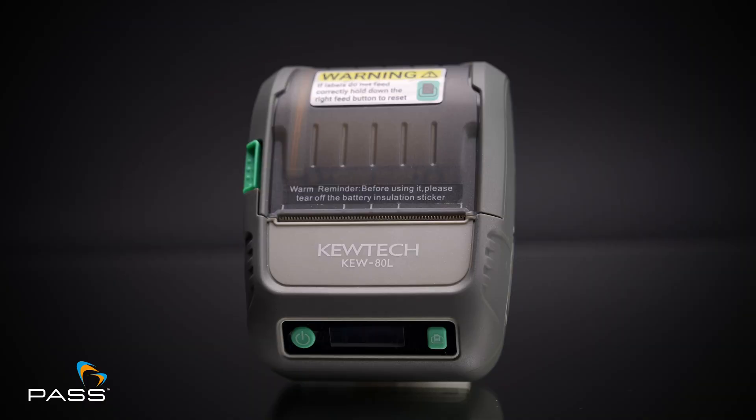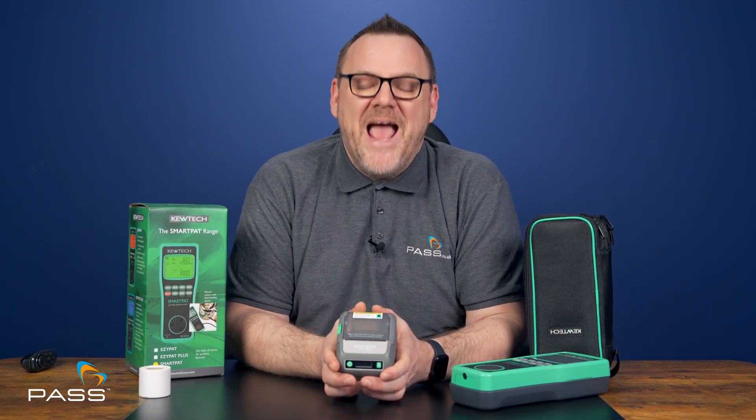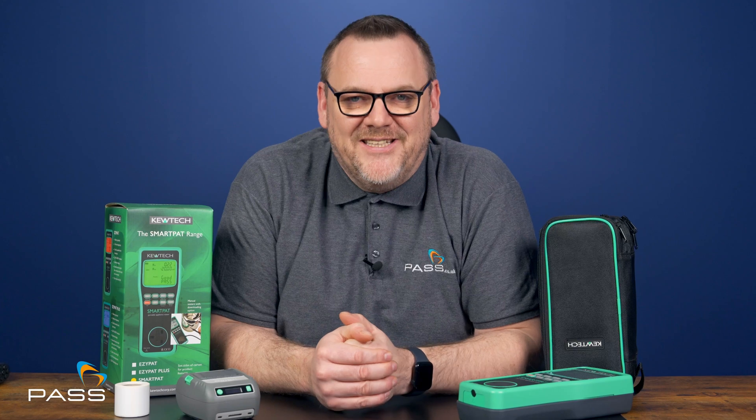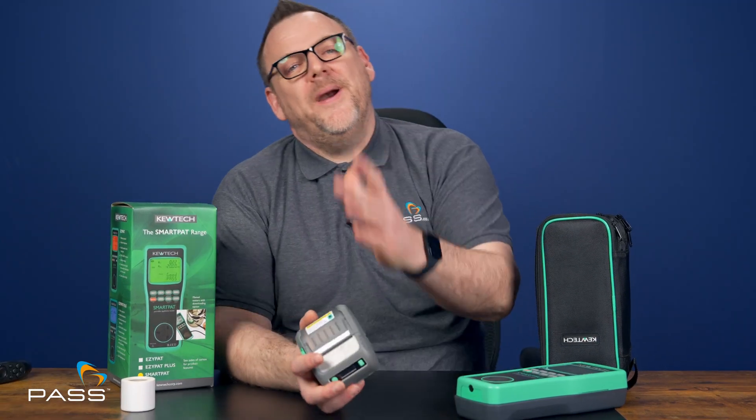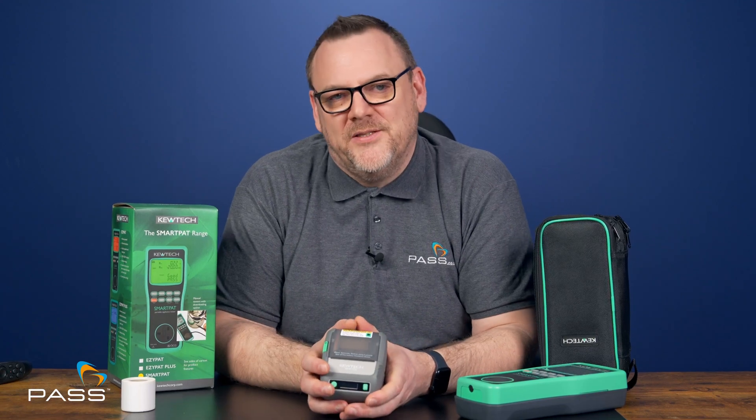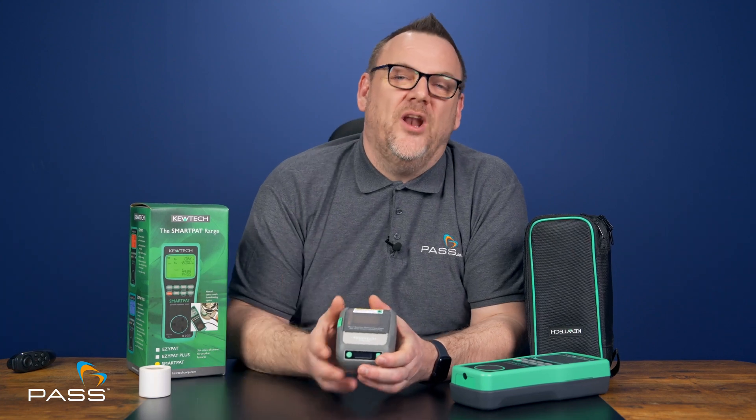The KEW-80L is compact, connects wirelessly, and lets you print durable labels that look professional every time. Here are some of the Smart PAT's key technical specs: it supports protective conductor resistance tests up to 20 ohms, insulation testing with 250 volt or 500 volt up to 20 megohms, and substitute leakage tests up to 12 milliamps. The KEW-80L printer is just as robust, with a rechargeable lithium battery and a mechanical life rated up to 50 kilometres of labels.